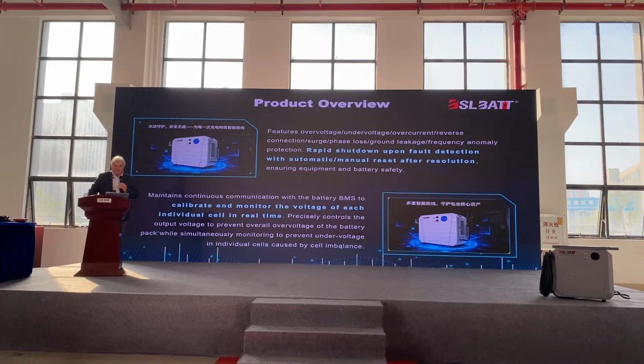It's built to calibrate and monitor individual voltages themselves. So if you've got a building running off grid power, or maybe a diesel generator backup, and that power changes or interrupts during the battery's charging cycle, the charger itself can modify and adjust so it's not affected by changes in the incoming power.